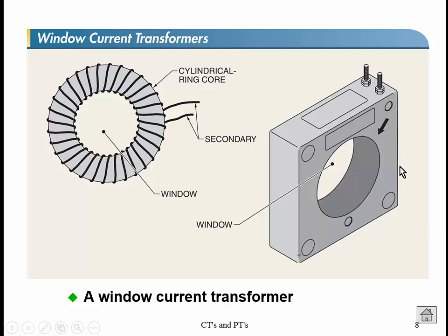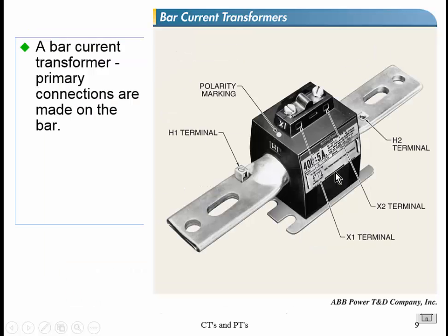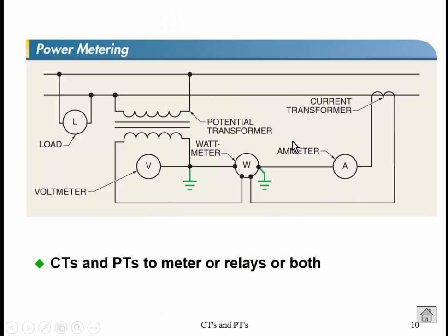Here's another look of a similar kind of window CT, or sometimes I think they call them donut CTs, or a bagel CT, or a Cheerio CT. We could call it all kinds of things. Now, the bar type, it's the same principle, but here's the conductor passing through, and you're just connecting the conductor with a NEMA connector, a 2-hole connector on either side. But again, it's the same principle, primary through the middle, and then the secondary going on the outside here.